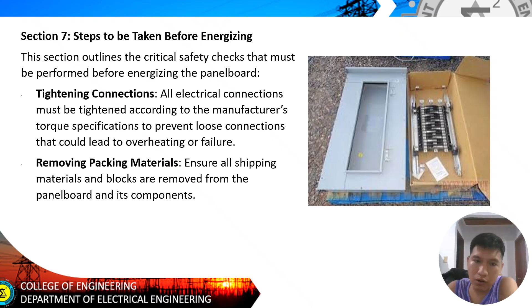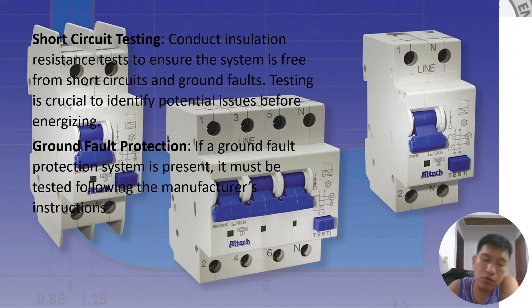Short circuit testing: we can conduct insulation resistance test to ensure that the system is free from short circuits and ground faults. Testing is crucial to identify potential issues before energizing. Also, ground fault protection - if a ground fault protection system is present, it must be tested following the manufacturer's instructions. Very simple - we need to test this before we energize or during energization.